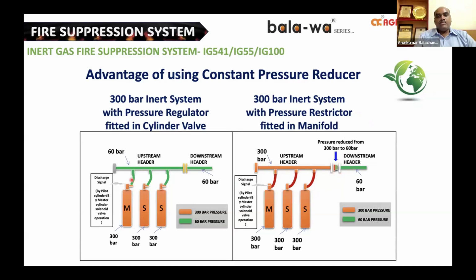In the new technology, we have an individual pressure regulator fitted in each cylinder valve, wherein it will convert the 300 bar to a constant flow of 60 bar right from the cylinder valve itself. And from our manifold, we'll be having 60 bar pressure. The major advantage is that since it's a constant flow system, it can be easily designed. The pipeline sizes and the nozzle orifices can be approximately and easily designed to achieve the design concentration, and thereby it is much more effective in suppression.